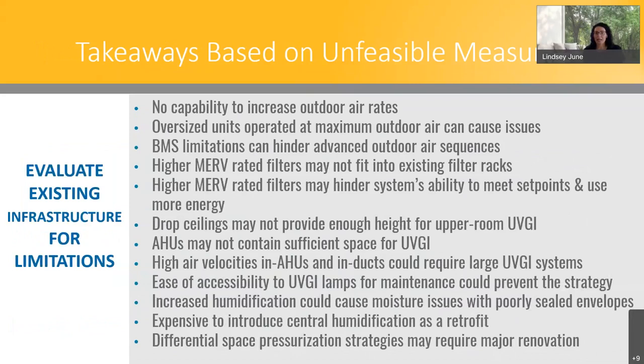So from the sample set of these pilot studies, the following considerations should be incorporated into evaluations to determine the feasibility of measures. So the first thing to consider is limitations of the existing infrastructure. So while there are a number of takeaways here, I'll just touch on a few in more detail. So there are several scenarios where outdoor air rates cannot be increased, such as units that are already right-sized, units that have fixed minimum outdoor air levels that can't be adjusted, 100% makeup air units, such as perimeter units in office buildings or healthcare critical spaces, such as labs or operating rooms.